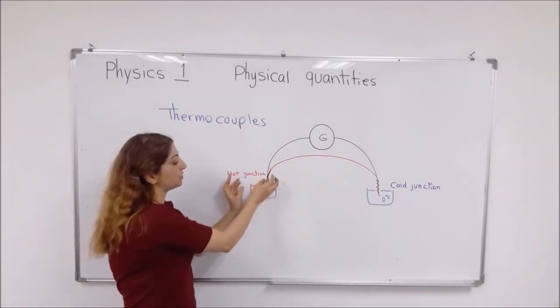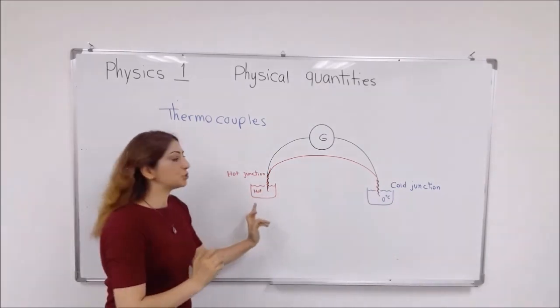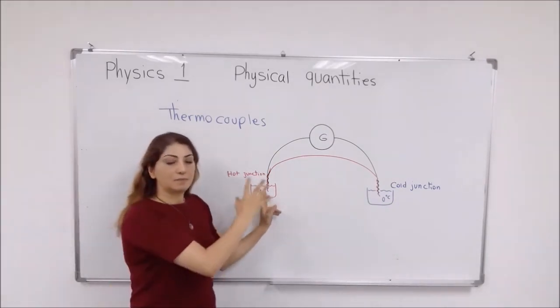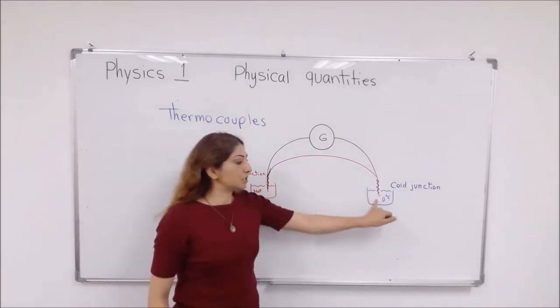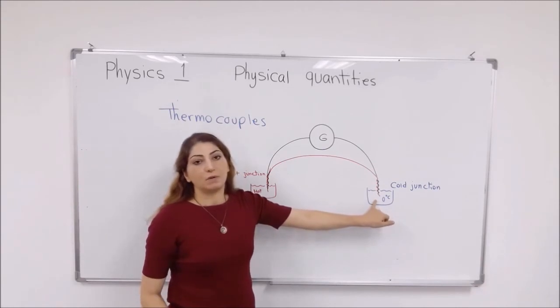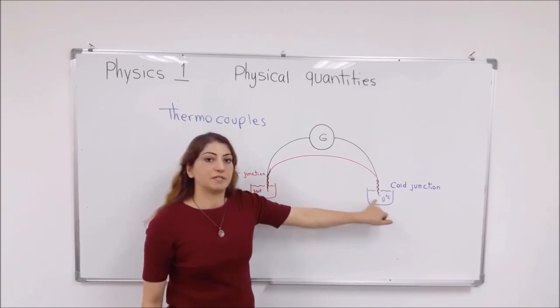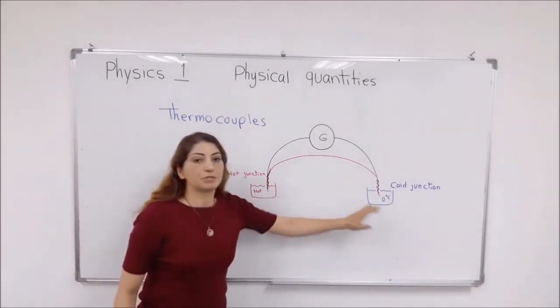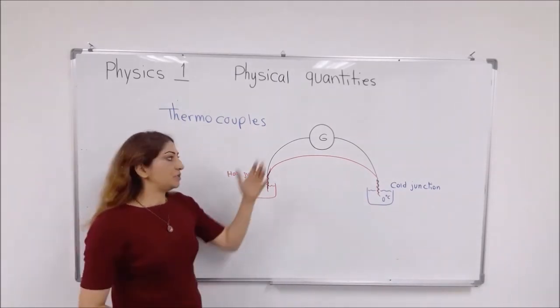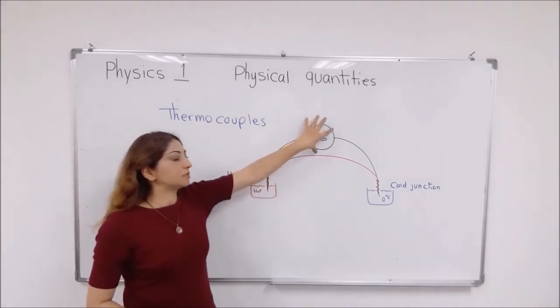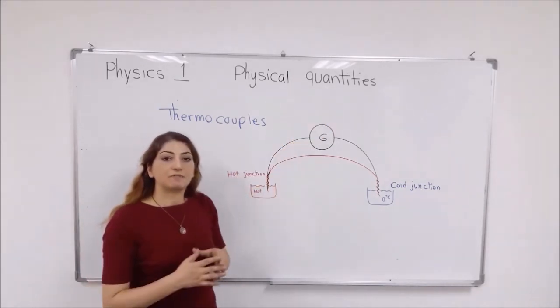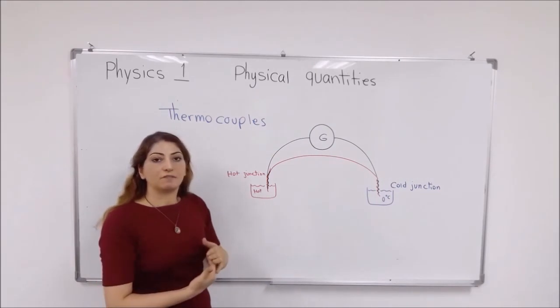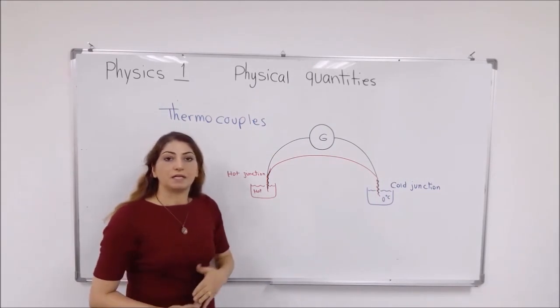They are joined together at two points here. And one junction is placed in a liquid or in a place that you want to measure its temperature, and the other junction is placed in a cold, very cold place like ice, which is zero centigrade degrees. So the difference between these two temperatures will be translated back into voltage on the voltmeter or galvanometer. Then you can find the temperature by bringing this value on the calibration curve.